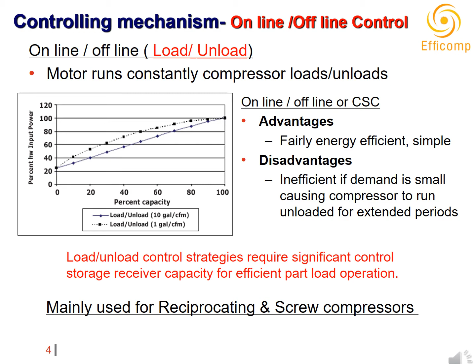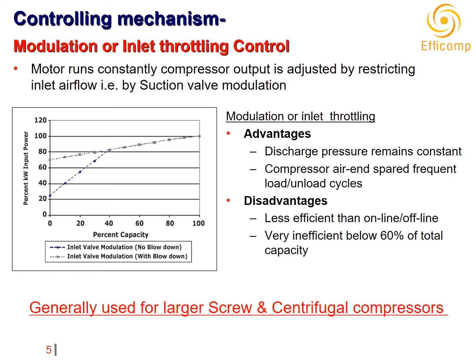Modulating inlet control allows the output of a compressor to be varied to meet flow requirements. Throttling is usually accomplished by closing down the inlet valve, thereby restricting inlet air to the compressor. This control scheme is applied to centrifugal and rotary screw compressors. This control method, when applied to displacement compressors, is an inefficient means of varying compressor output. When used on centrifugal compressors, more efficient results are obtained, particularly with the use of inlet guide vanes, which direct the air in the same direction as the impeller inlet. The amount of capacity reduction is limited by the potential of surge and minimum throttling capacity.